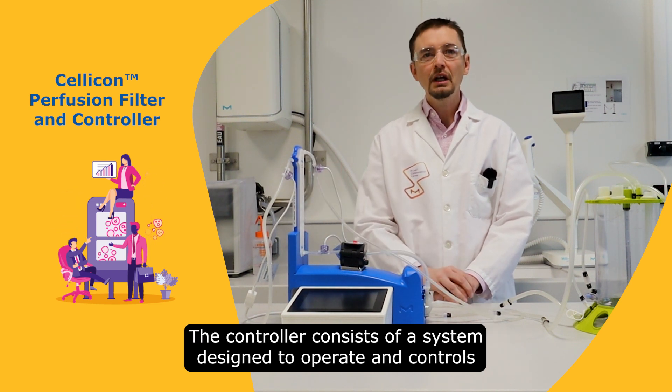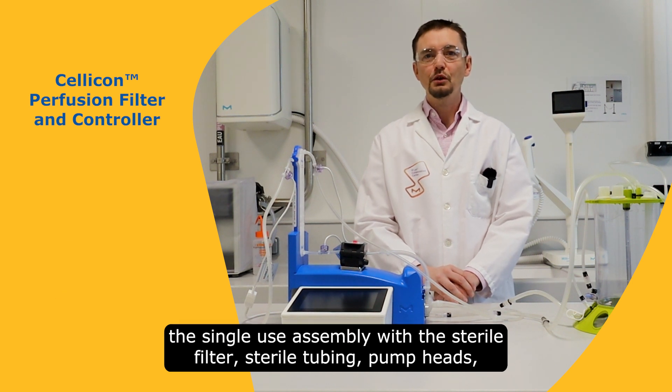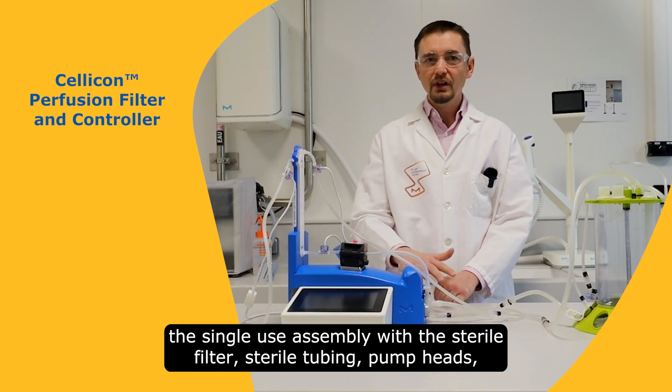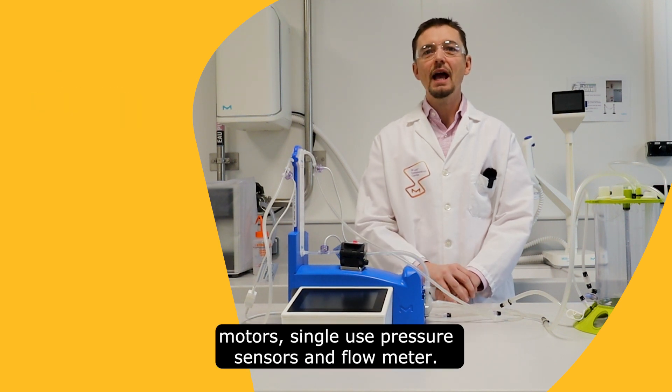The controller consists of a system designed to operate and control the single-use assembly with the sterile filter, sterile tubing, pump heads, motor, single-use pressure sensor and the flow meters.